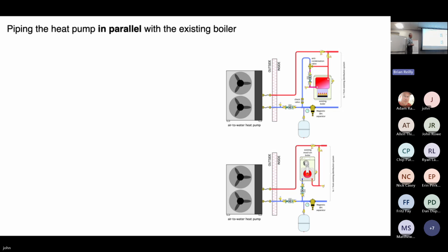Thank you. Bottom line on piping boilers with heat pumps: you pipe them in parallel, not in series. There are very, very few times when it's ever a good idea to put multiple hydronic heat sources in series with each other. By series, I mean you go into heat source A, you come out, then you go into heat source B, and then you go back to the system. There are a lot of downsides to that.